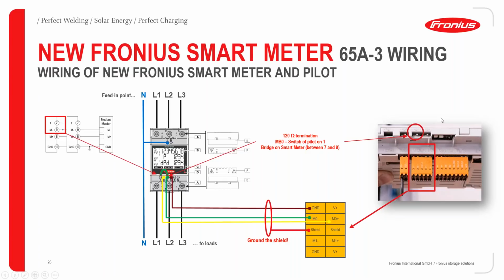Please be sure to terminate it correctly here on the smart meter, and also on the pilot we have got this termination switch, which is 0 or 1. If it's set on 1, that means the termination resistance is set always on the end of the communication line.